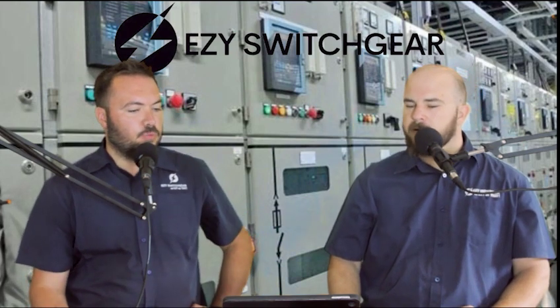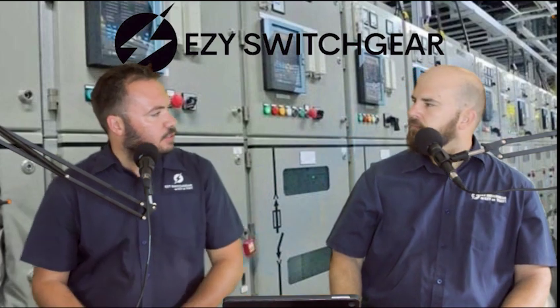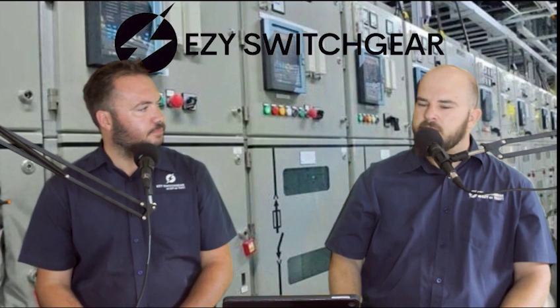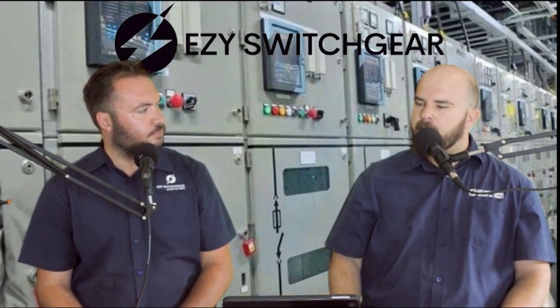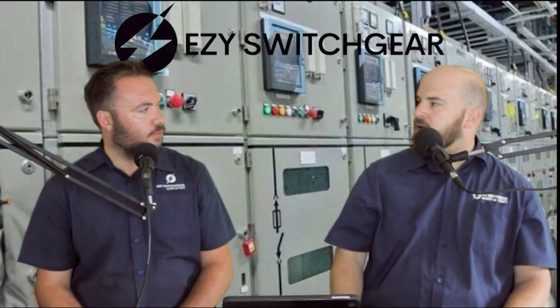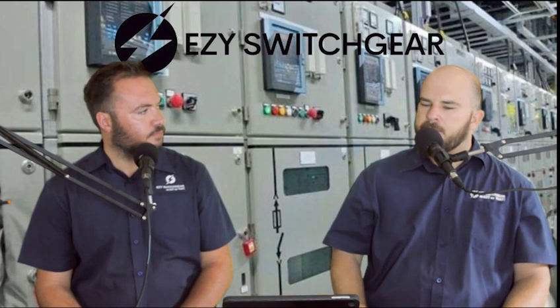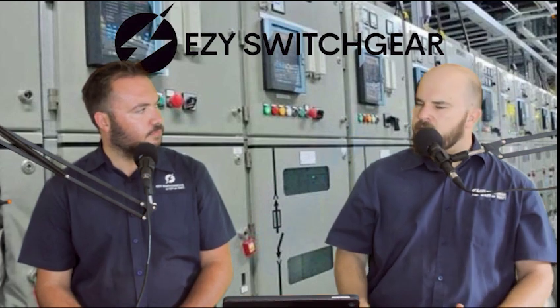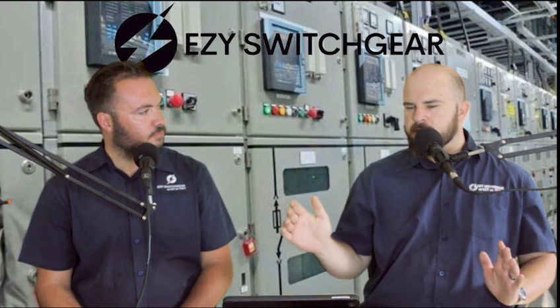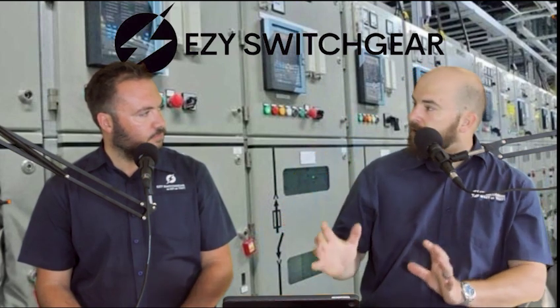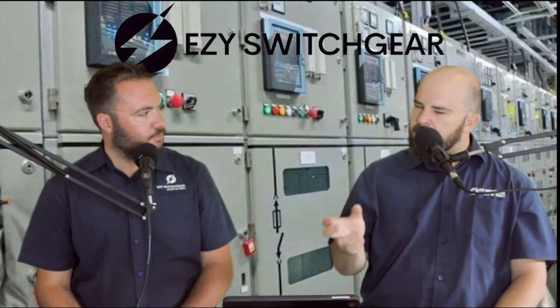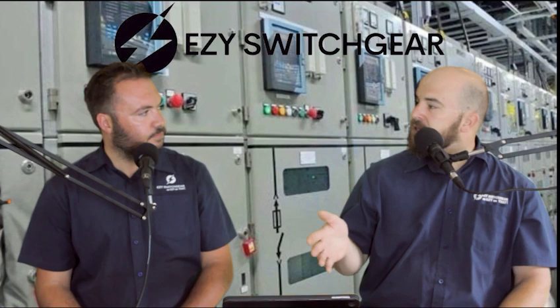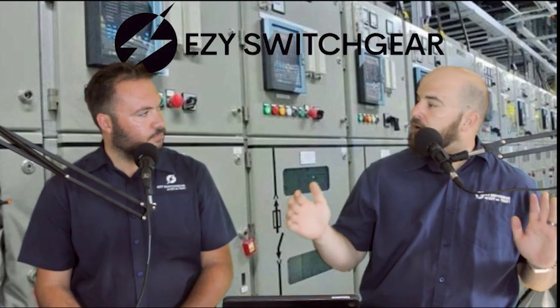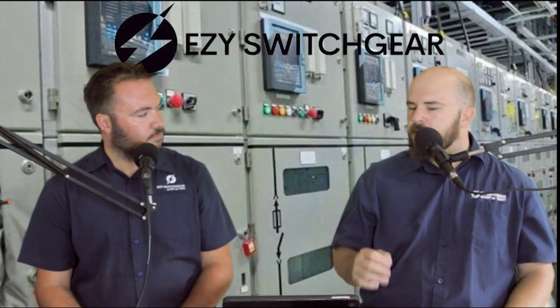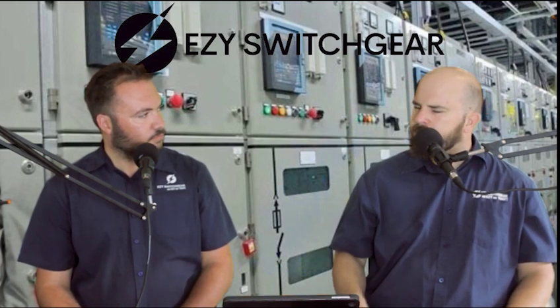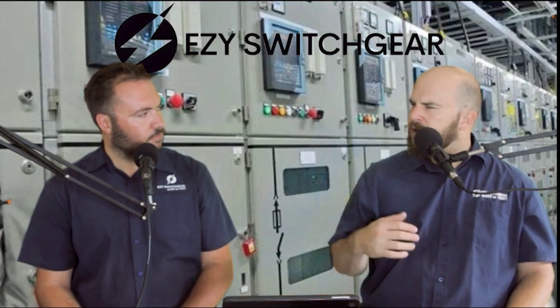Okay. Then the next one is the solid insulated switchgear, which we don't see a lot. Yeah, so there are a few brands of solidly insulated switchgear. They work quite well, but when you need to repair something, it is quite a mission. Because you cannot get in there, it's not very common. So you get air insulated switchgear a lot, especially in your primary subs, and you get gas insulated switchgear, especially in dirty environments. And then you get solidly insulated switchgear, but mostly in secondary applications. There's almost no solidly insulated primary panels. I don't even know of one. So solidly insulated is not a very common thing, and therefore it's not something that is regularly covered.